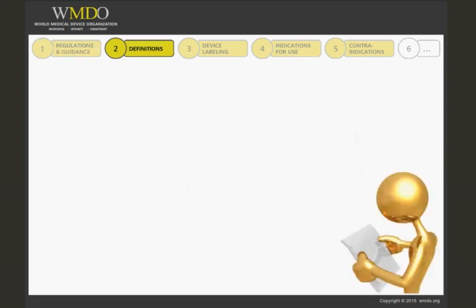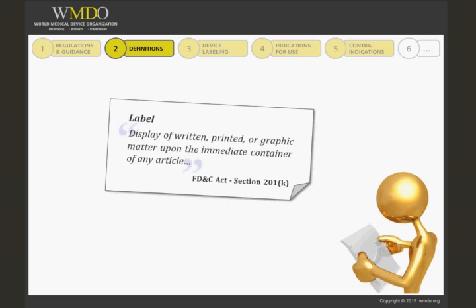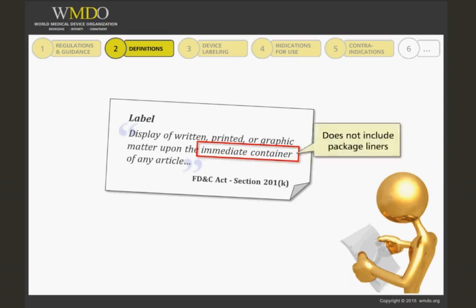Let's have a look at the definitions applicable in the U.S. The Federal Food, Drug, and Cosmetic Act, Section 201-K, defines label as a display of written, printed, or graphic matter upon the immediate container of any article. The term immediate container does not include package liners. Any word, statement, or other information appearing on the immediate container must also appear on the outside container or wrapper, if any there be, of the retained package of such article, or is easily legible through the outside container or wrapper.